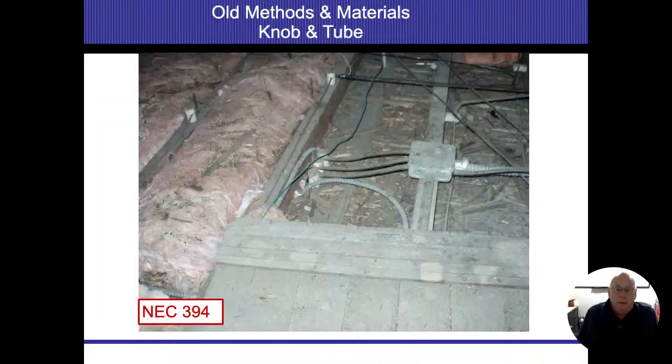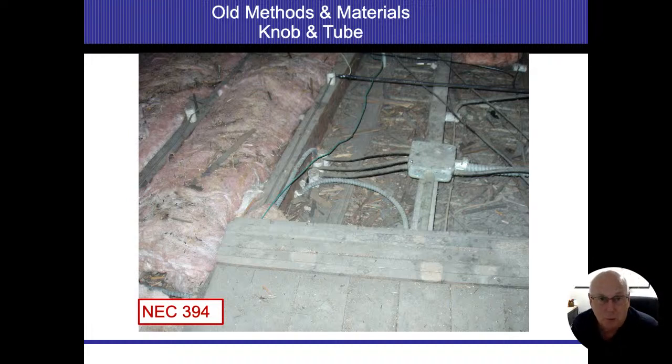Knob and tube. There are a lot of insurance companies now that don't want to insure homes that have knob and tube wiring in it. And it's kind of a big deal when we come through it. Identifying it, to me, it's a problem. I let my clients know. I have them check with their insurance companies if we run into it. It's not a mandated defect that we tell people, because the wires are tin-clad copper that we normally see.